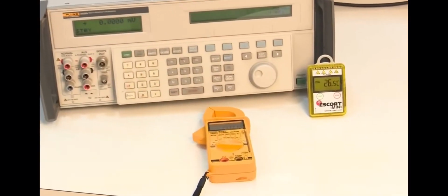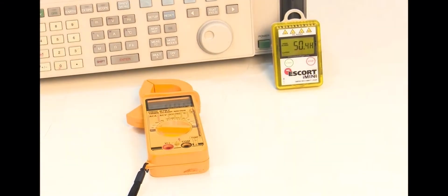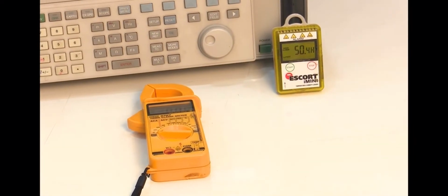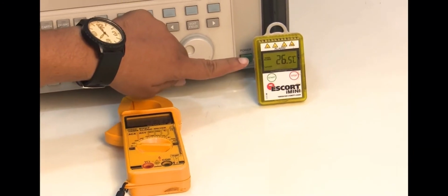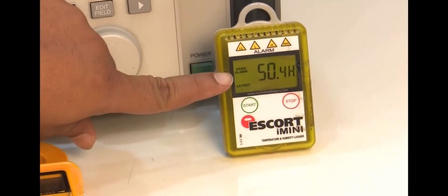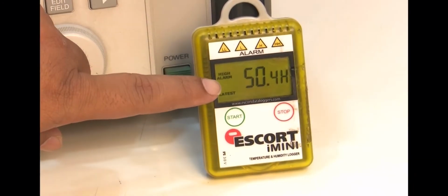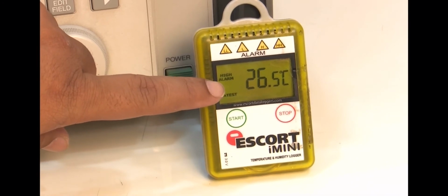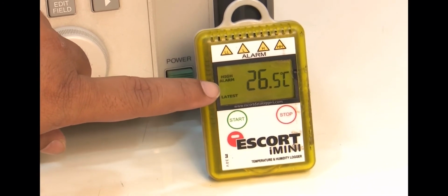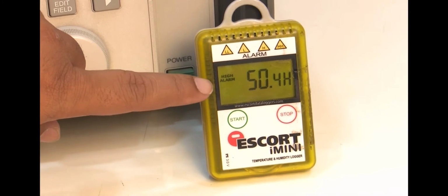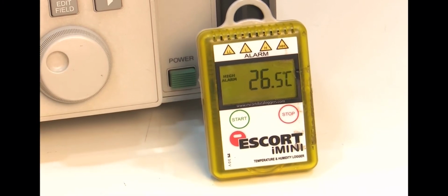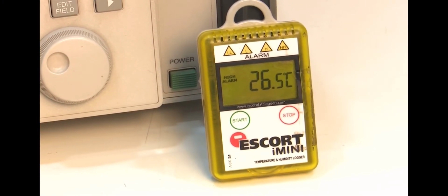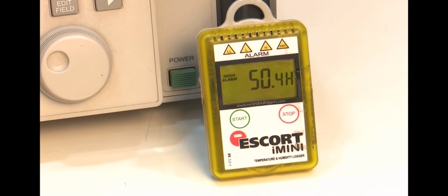Keep the digital clamp meter for at least 30 minutes for soaking at 25 plus minus 2 degrees centigrade so that the temperature is brought to equilibrium. Before starting calibration, warm up UUC for at least 30 minutes and ensure that the environment condition is maintained. The temperature should be between 25 plus minus 2 degrees centigrade and humidity should be 45 to 75% RH.